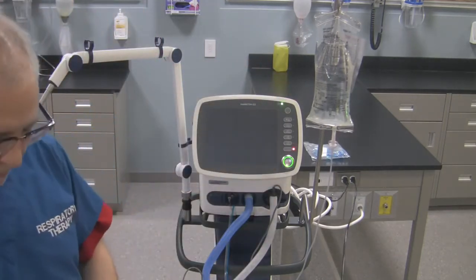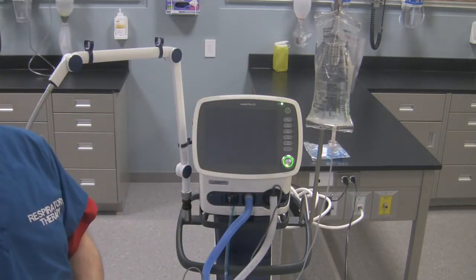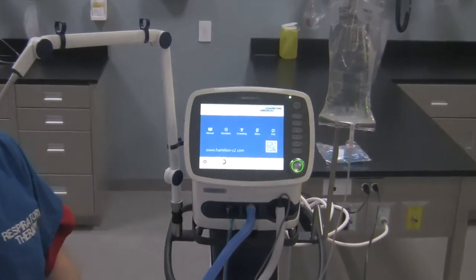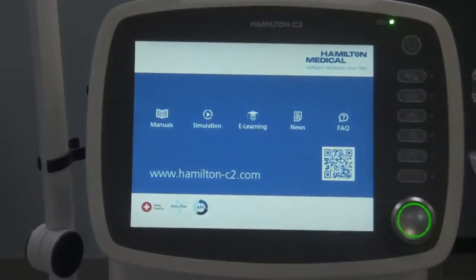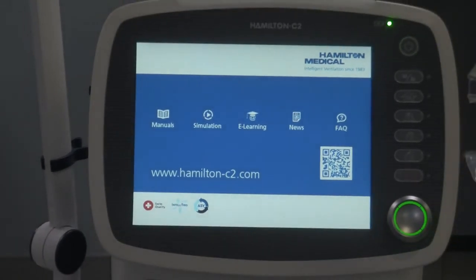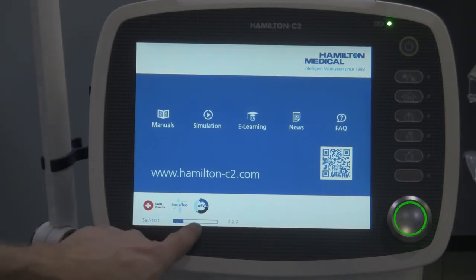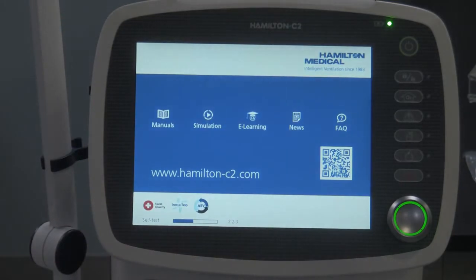The ventilator is going to make a noise, and it's going to start powering up. It goes to this screen right here. And what you're going to see at the bottom here right away is the little time bar for the self-test that it does. So it says self-test right over here. Now it's doing its own little internal self-test on the brains of the ventilator per se. All right. It checks itself out.